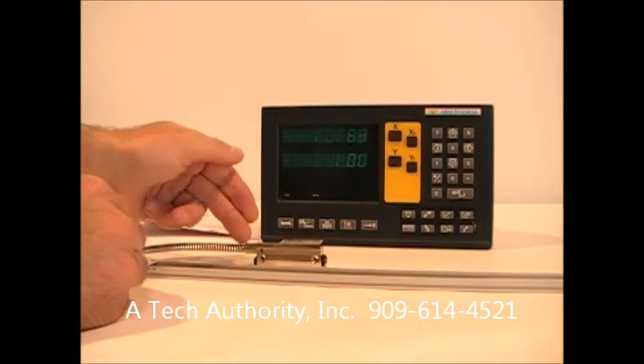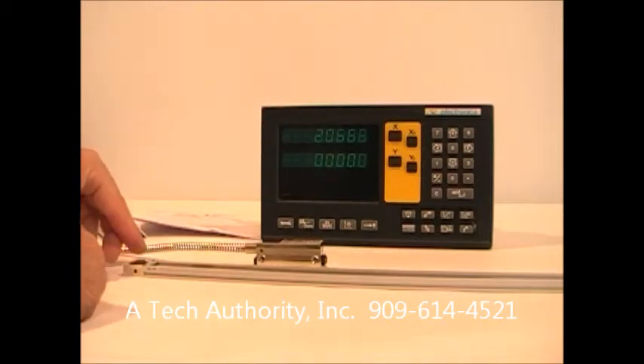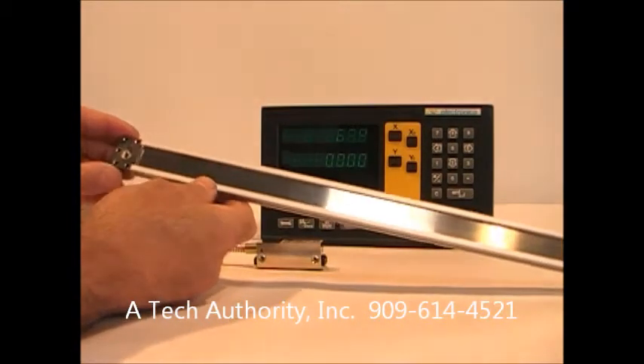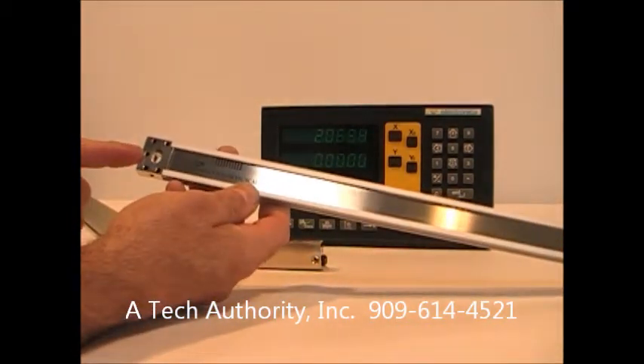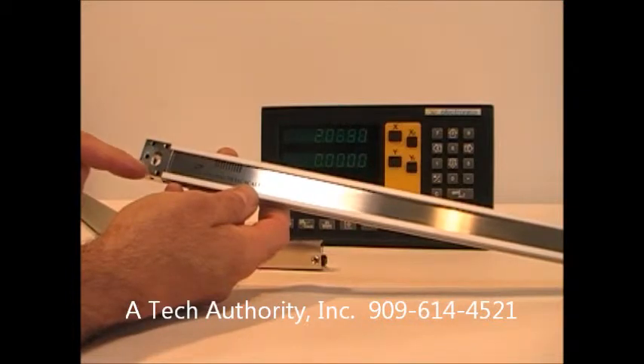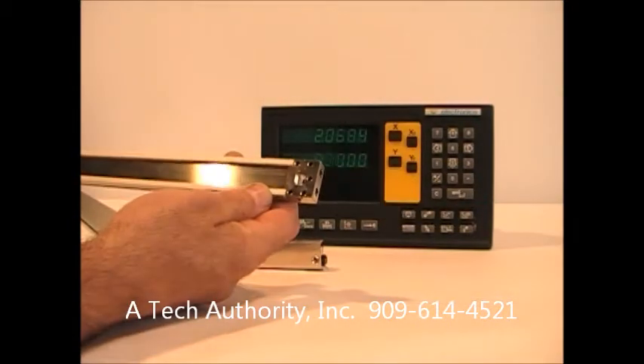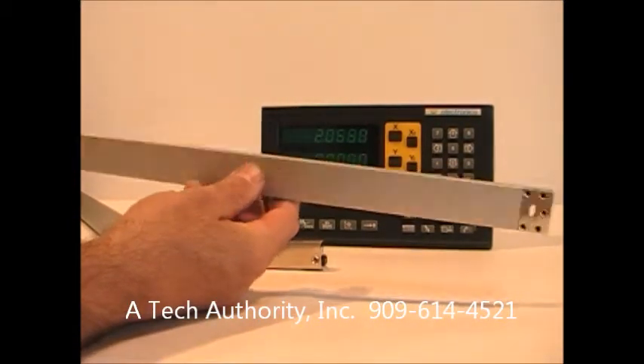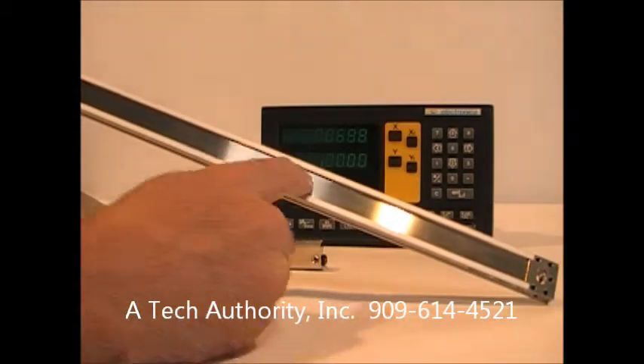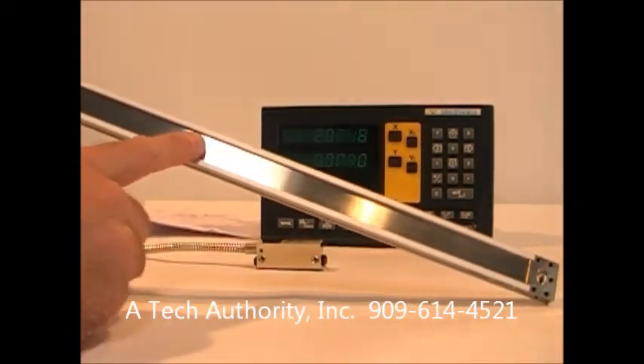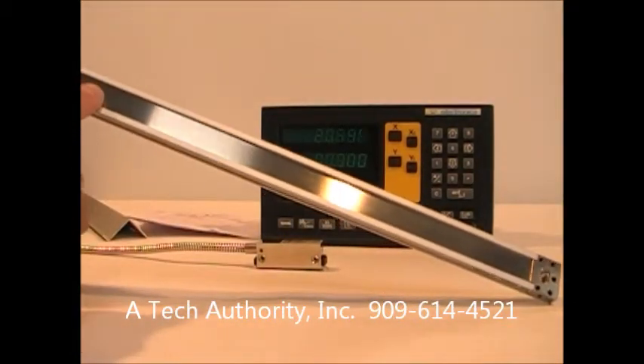It is a hard soldered cable with a DB9 on the back. The scale itself has stainless steel end caps and a series of jack screws to help level and true the install on both sides. You've got the aluminum housing and a cover here that gives protection to the north-south magnets below.